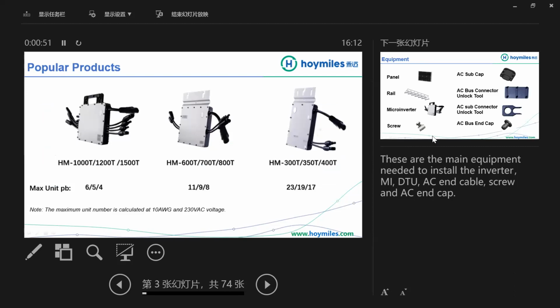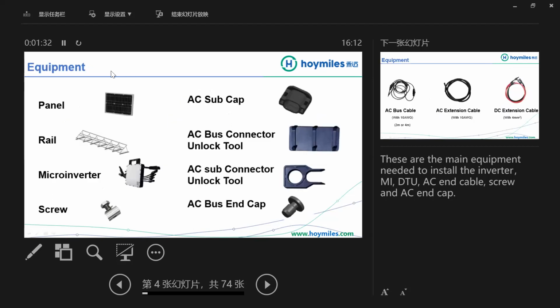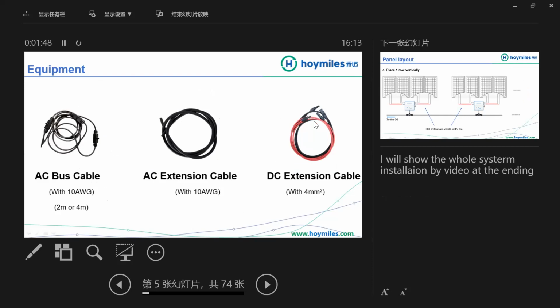Before that, as we know, the HM series is our popular product. We have three types: single unit, 2-in-1 unit, and 4-in-1 unit. And each type has three models. The suffix T means the trunk, meaning it is connected by bus cable. The maximum unit per branch depends on the model you choose. For example, if you choose the HM 1500T model, the maximum unit per branch is 4. It is noted the maximum unit number is calculated at 10 AWG line and 230 grid voltage. The equipment we need is panel, rail, microinverter, screw, AC subcap, AC bus connector unlock tool, AC sub connector unlock tool, AC bus end cap, AC bus cable, AC extension cable, and DC extension cable.